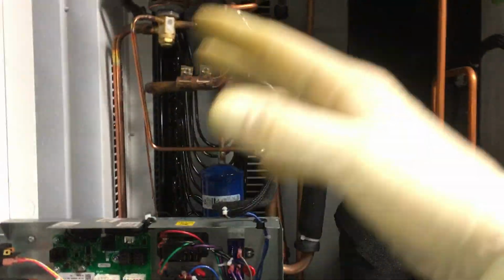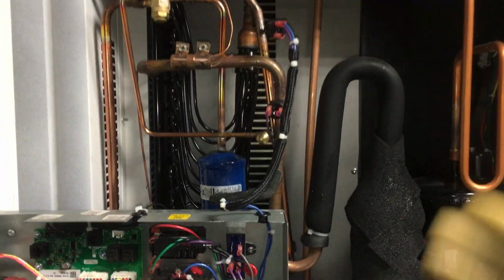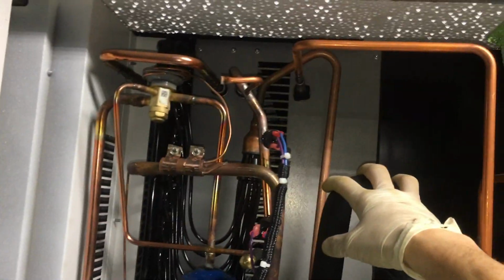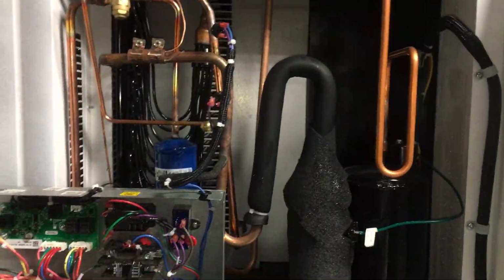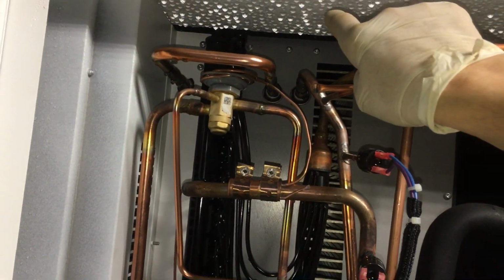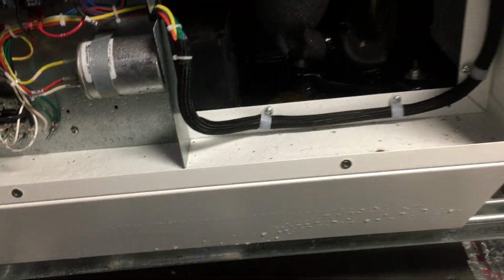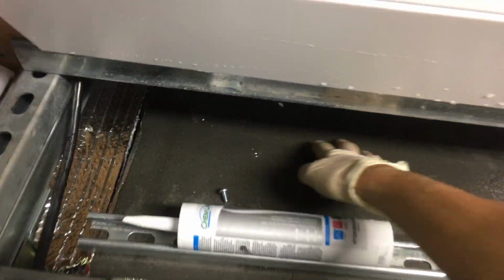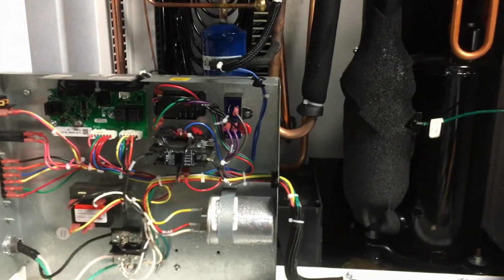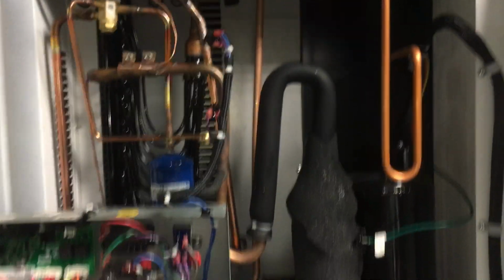So this is a process that we're going over, showing you an example here of running a piece of equipment in an ambient condition that it was never meant to be run in. So I'll fix this by insulating all the cabinets on the outside, so the temperature will never get cold enough to reach the condensate point, and that'll take care of all this leakage that's happening down here where it's turning to water and pouring off, which I kind of knew was going to happen. I told them it shouldn't be put outside, but they had to because of the size restriction. The room was not developed right, it wasn't sized right.